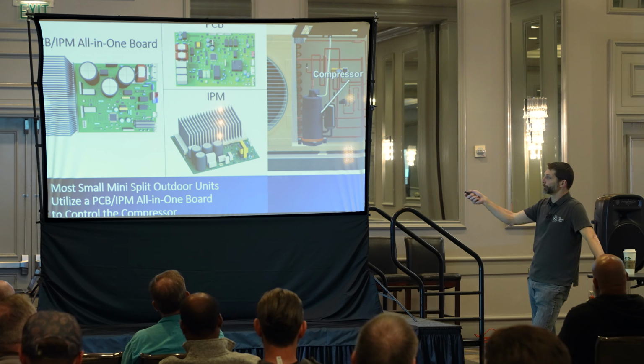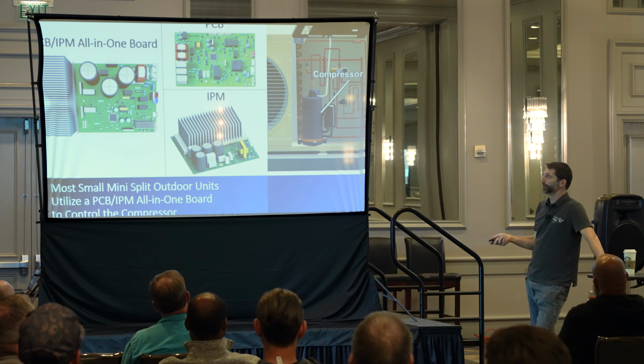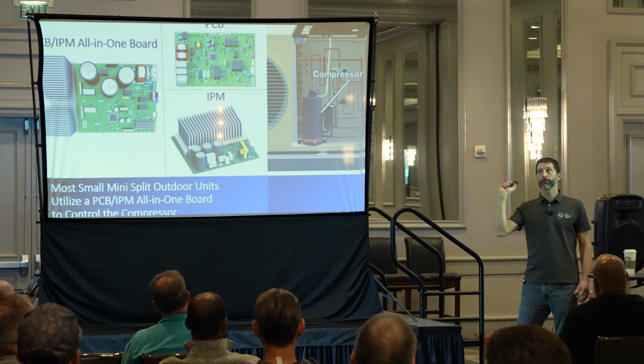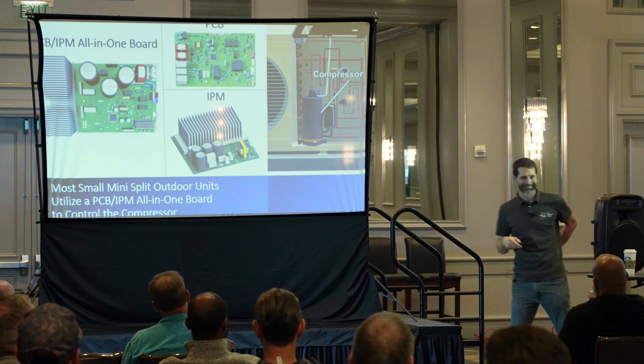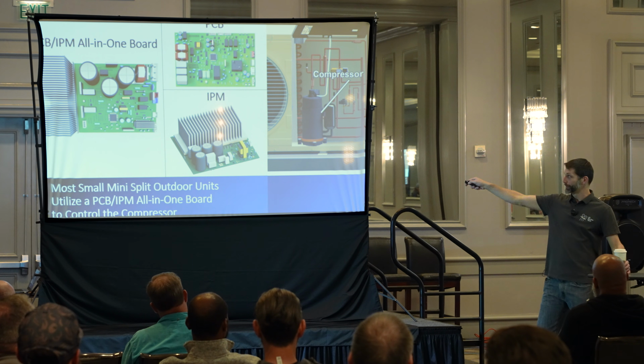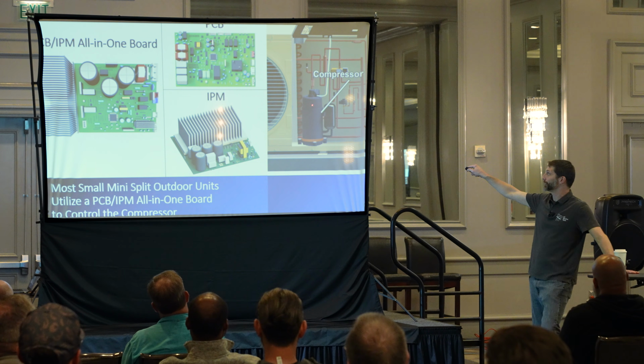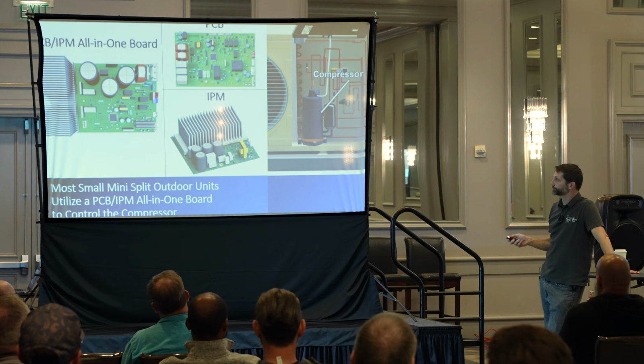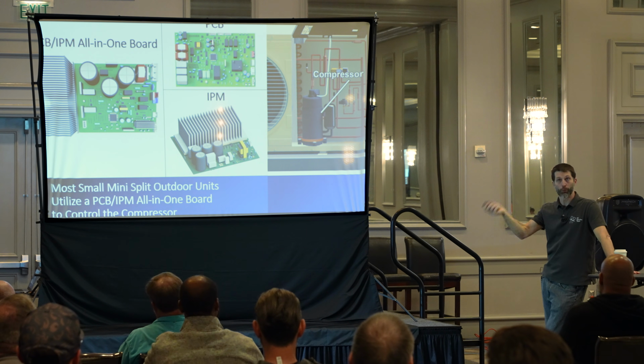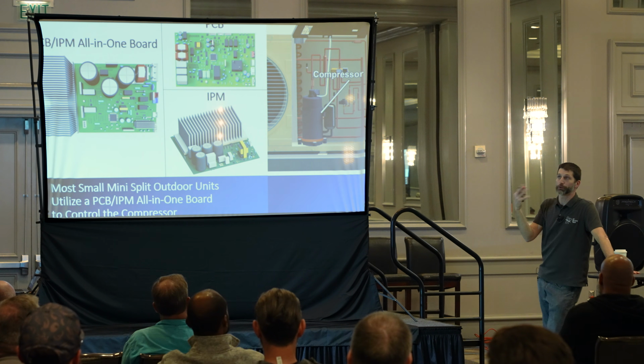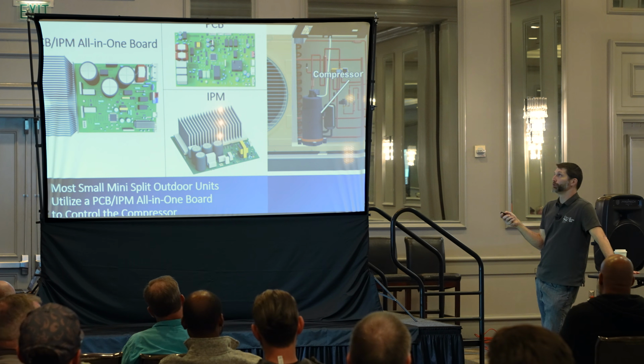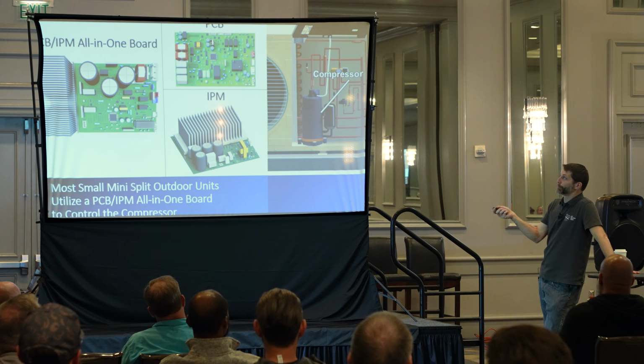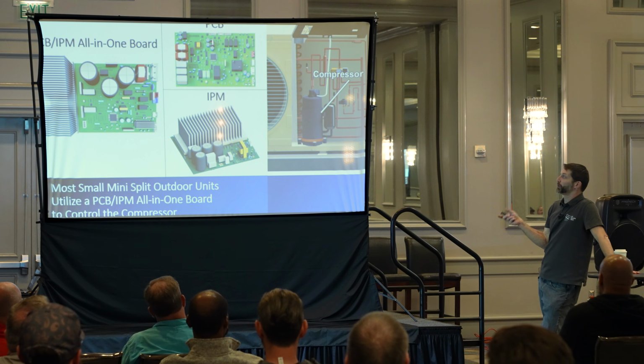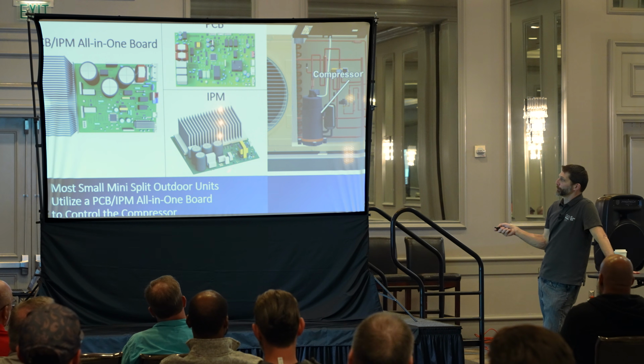People are having boards fail just due to pulling the disconnect. It even happens on ECM indoor motors, like on air handlers and furnaces now. The shock is being absorbed in the circuit board that's powering the compressor or the fan motor. So that's what I'm going to tell you to do. Put it in standby mode, wait for the compressor to stop, then pull the electrical disconnect in order to service it. As well, if you're trying to check electrical resistance values, say on the back of an IPM, you want to wait 5 minutes and allow the capacitors to discharge by themselves. They'll automatically discharge, but you have to give them a little bit of time.